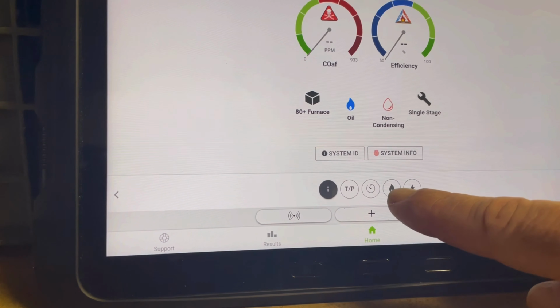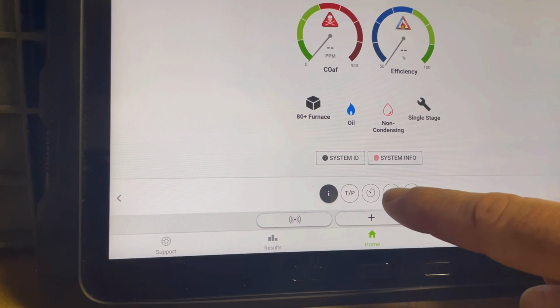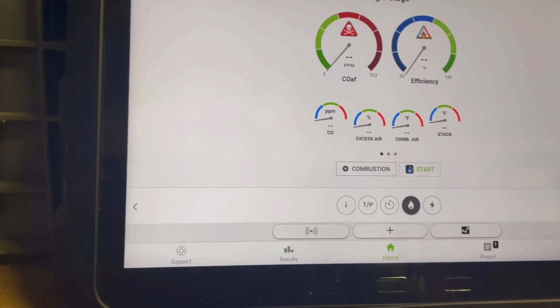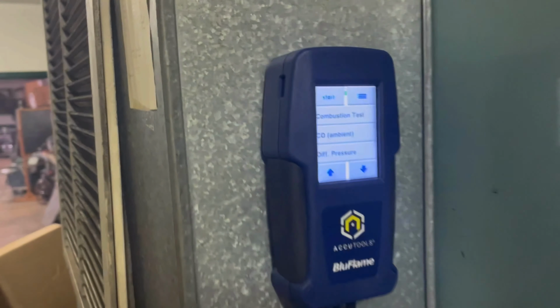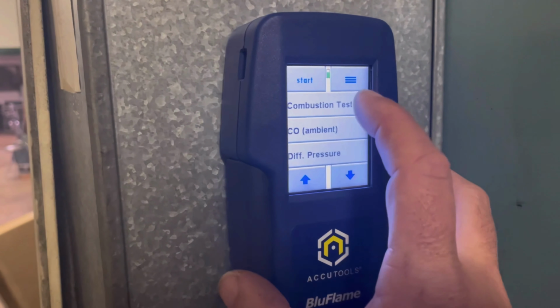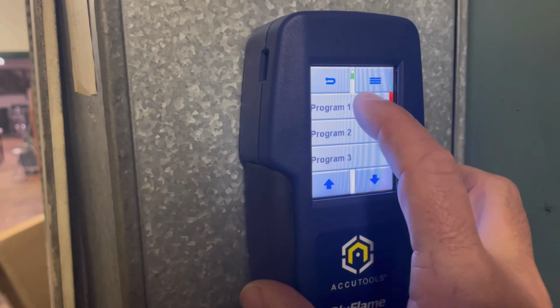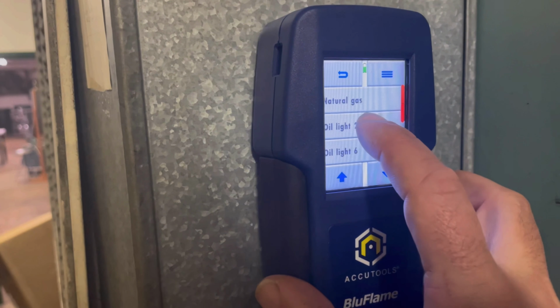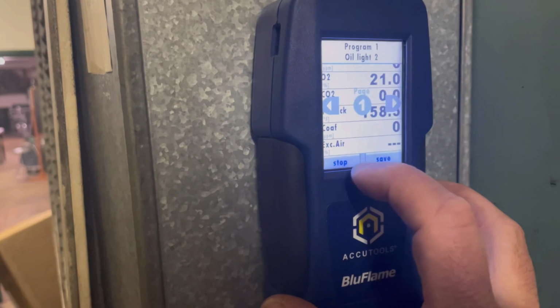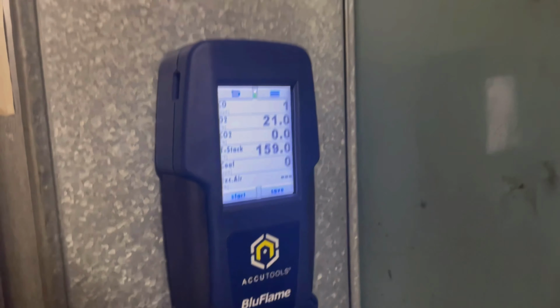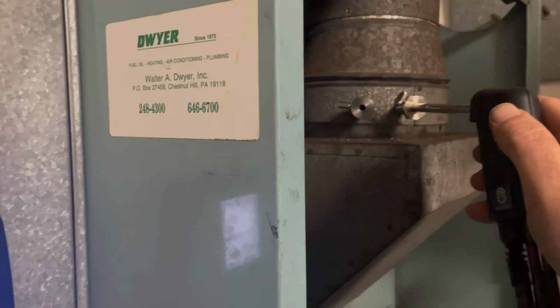So here I am opening up the app and connecting the analyzer. It's very easy to do, and again, I'm doing this one-handed. Now I have the tool set up. I press the combustion button, press the program 1 to light oil, and press stop because the pump starts when you press that button. Now I insert the probe.